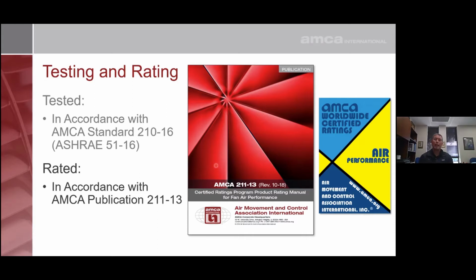ship the fan and the documentation for the performance off to AMCA, who acts as a third-party validation organization. And they have to be able to represent our data roughly plus or minus 2.5% on flow and pressure, 5% on energy consumption. And if they can do that, then we can certify our product. And that product will be certified for 3 years. What's to assure that over a period of time, up until 3 years, that a fan is going to maintain its fan performance?